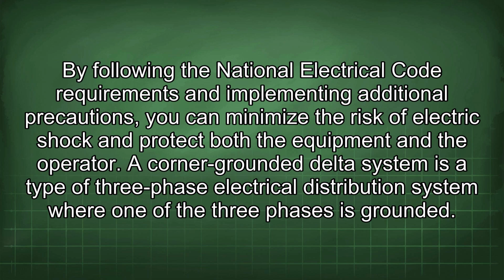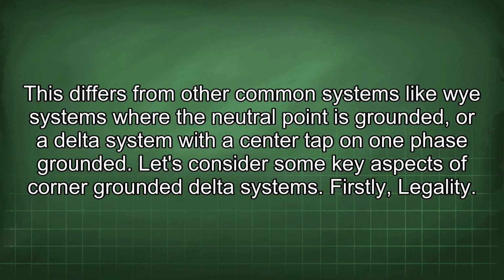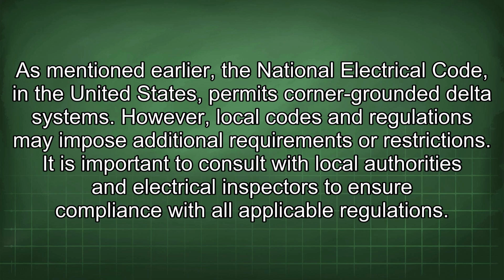A corner-grounded delta system is a type of three-phase electrical distribution system where one of the three phases is grounded. This differs from other common systems like Y systems where the neutral point is grounded, or a delta system with a center tap on one phase grounded. Let's consider some key aspects of corner-grounded delta systems. Firstly, legality. As mentioned earlier, the National Electrical Code in the United States permits corner-grounded delta systems. However, local codes and regulations may impose additional requirements or restrictions. It is important to consult with local authorities and electrical inspectors to ensure compliance with all applicable regulations.